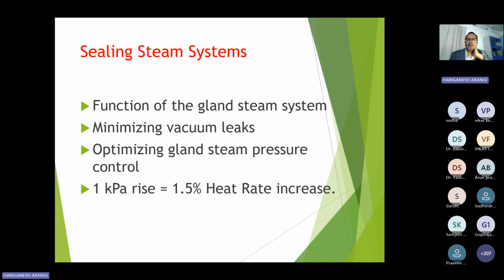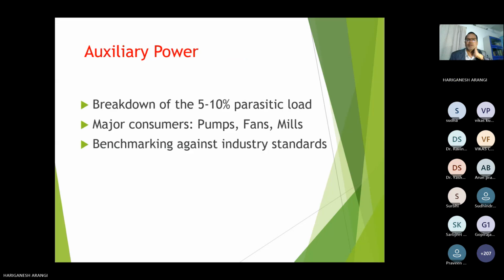The sealing steam system, what we have discussed. Auxiliary power, as a normal thumb rule, is approximately 5 to 10% of the total capacity of the plant; that auxiliary consumption will be there. That 5 to 10% auxiliary consumption also we can effectively minimize by using, as we discussed, VFD drives.